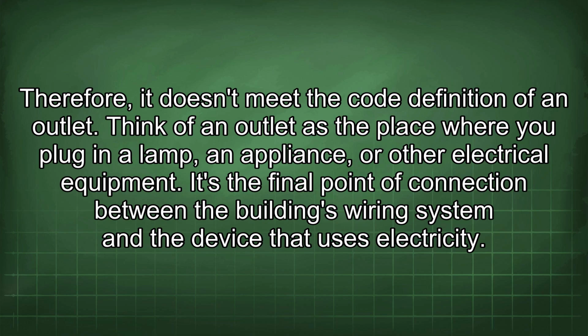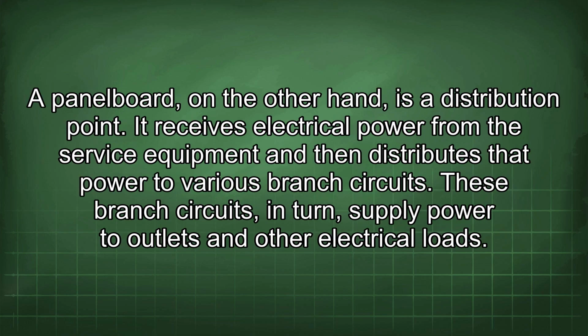Think of an outlet as the place where you plug in a lamp, an appliance, or other electrical equipment. It's the final point of connection between the building's wiring system and the device that uses electricity. A panel board, on the other hand, is a distribution point. It receives electrical power from the service equipment and then distributes that power to various branch circuits. These branch circuits, in turn, supply power to outlets and other electrical loads.